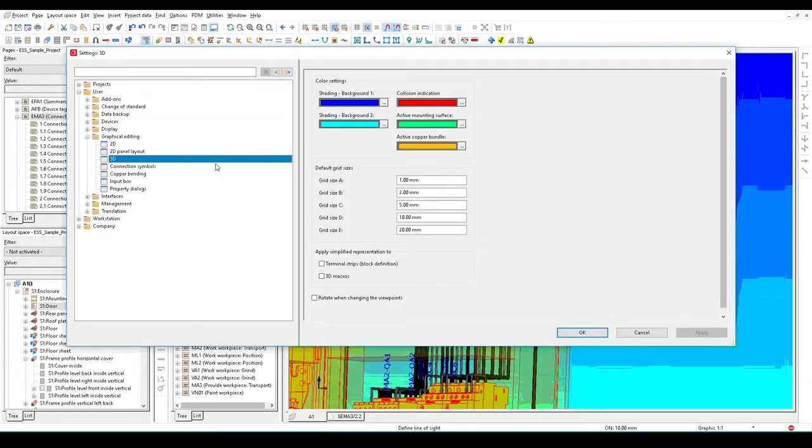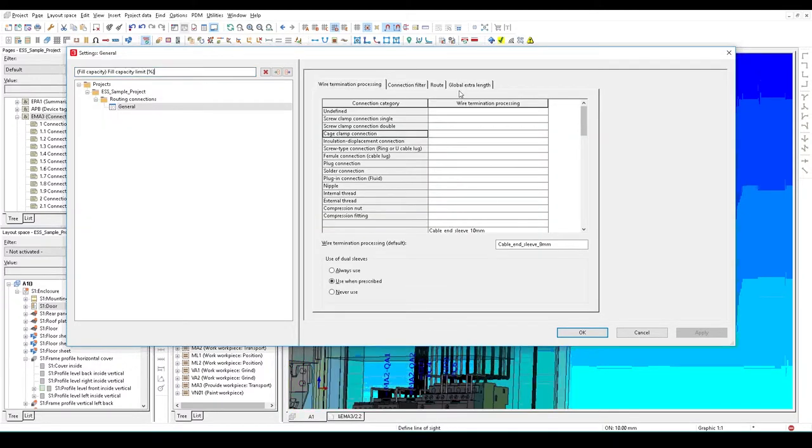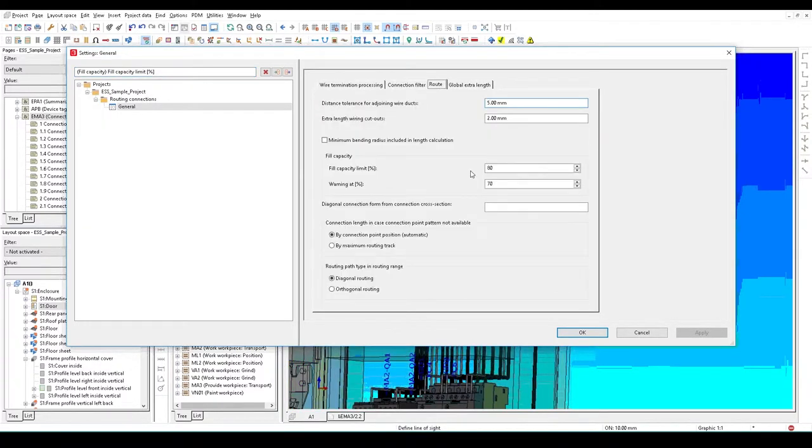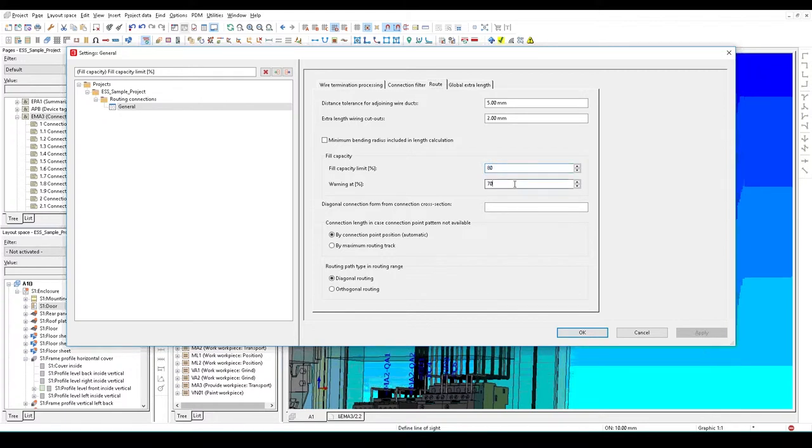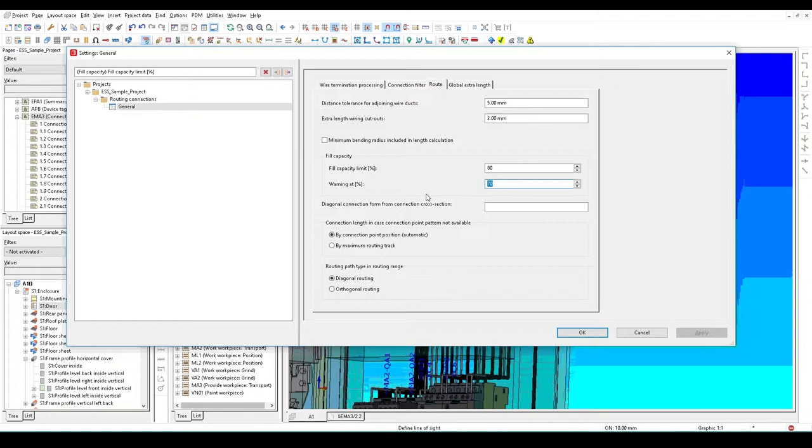If I move to fill capacity limit, when I do my routing I can say I never want to fill up trunking more than 80%, with a warning at 70% to show I'm getting close. This means right from the start, the panel builder and electrical engineer are helping each other by putting data in the front, passing it to the panel builder. He knows he's got the right size trunking, and the technician's not going to have a problem implementing this.